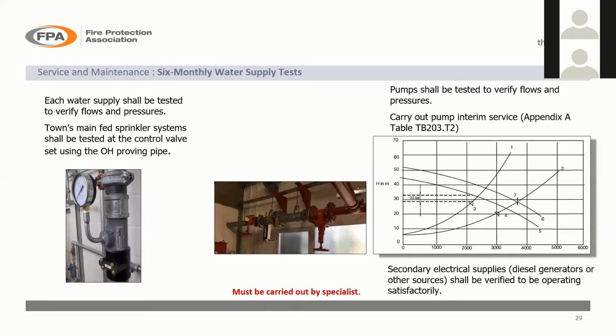Six monthly, the water supplies need to be tested, whether that's a town's main test through what they call a proving pipe, which is shown in the picture on the left there, or if it's a pump and tank, you need to test it using test return pipework, such as that shown in the picture in the middle there. If it's a pump system, you'll be looking to produce a pump curve, similar to the one on the right-hand side there.